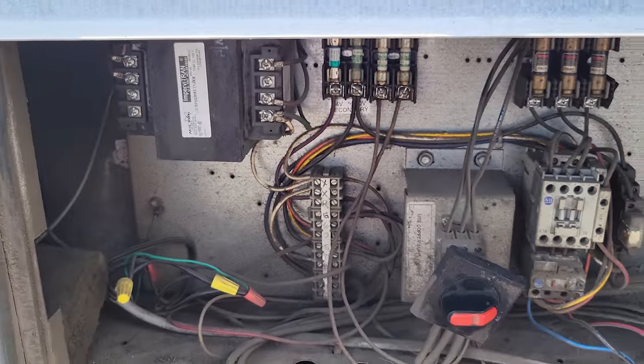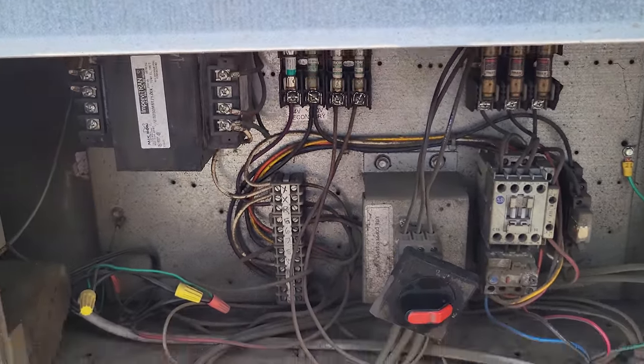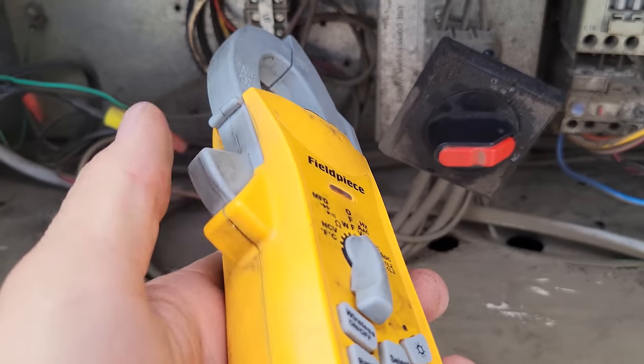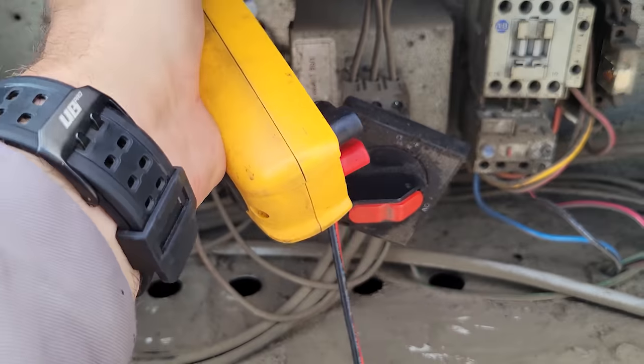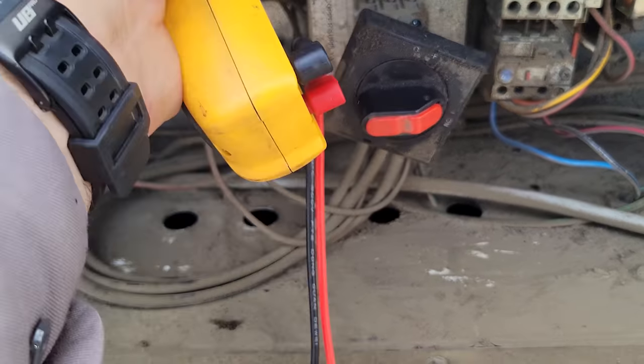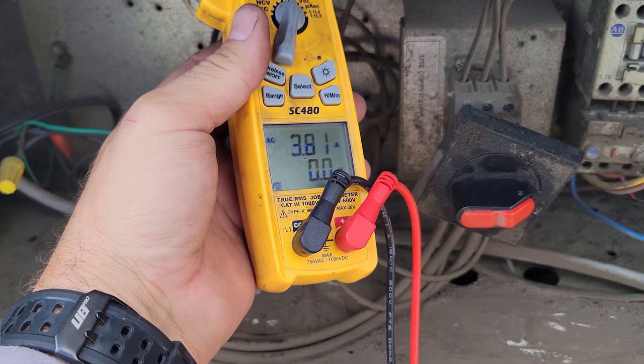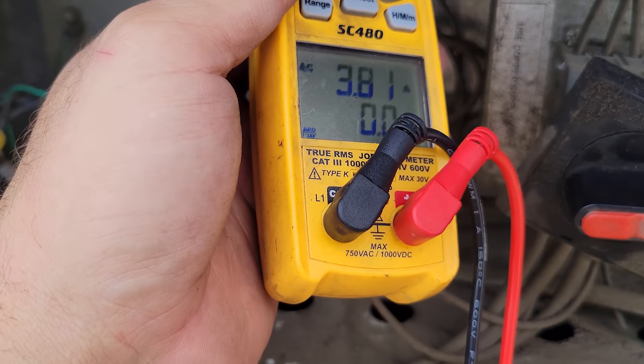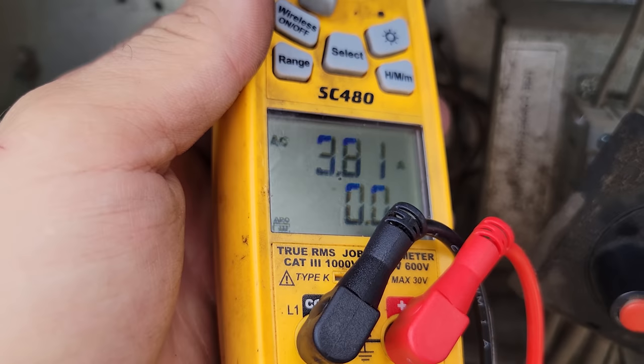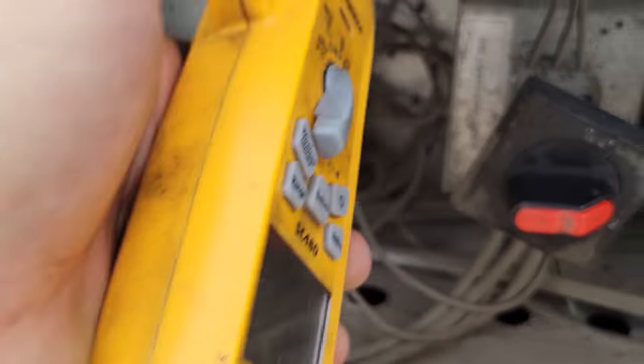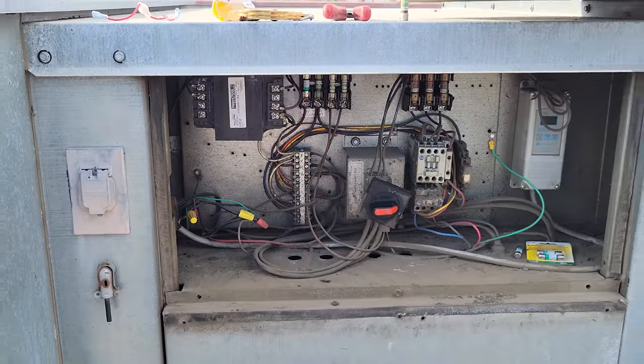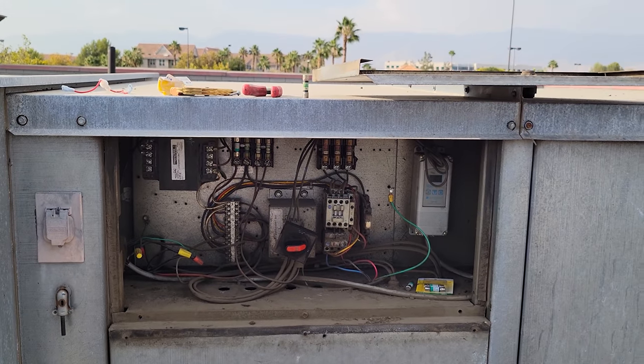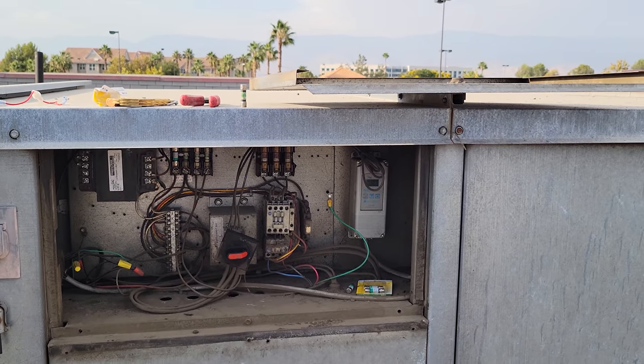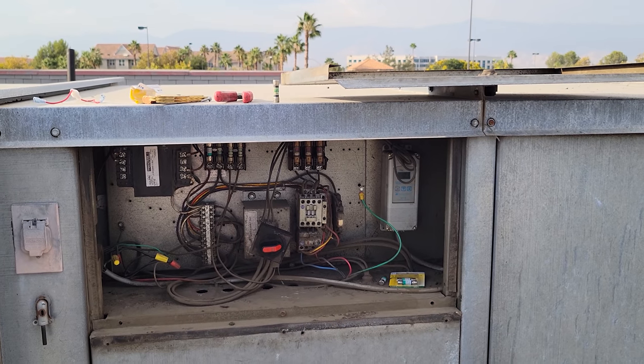But I will say I did check current on that wire earlier, and it was barely anything. Let's see if we can check it again. Three amps? That's not bad at all. So 3 amps, it's a 10 amp circuit. That's fine. So yeah, this was a trip. Shut down the entire building. They had to close the doors. Well, luckily I was close.